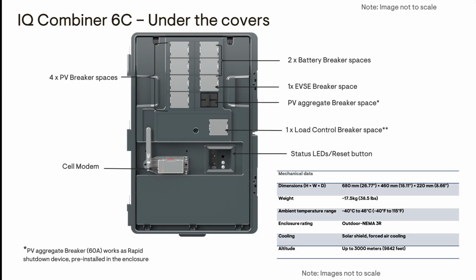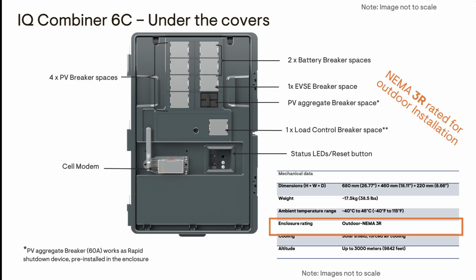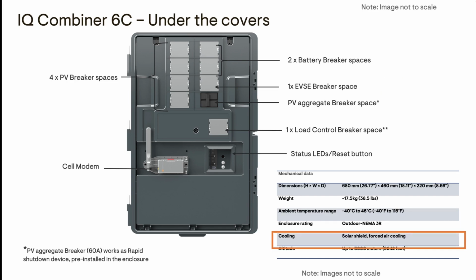The Combiner 6C, though larger than its predecessors the Combiner 5 or 4, is still a relatively compact box. It is around 26 inches tall, 18 inches wide, and 9 inches deep, and weighs in at a mere 40 pounds. It is NEMA 3R rated for outdoor installation and use. And because there are many electrical things that connect into it, we have some really good thermal management.